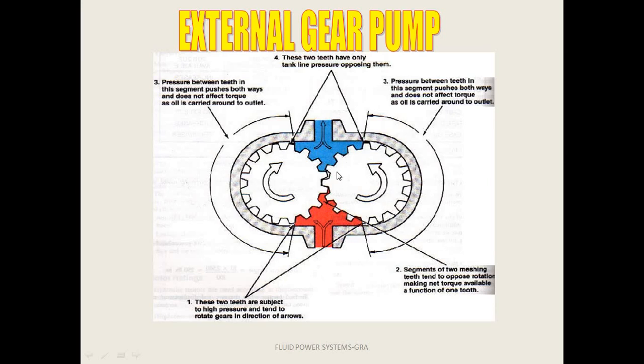Right? The second limitation is the volumetric efficiency of gear pump is very less. What I am trying to say here is, from this outlet side to the inlet side there will be leakage. Whatever the fluid will be coming here, a part of it will drain back to the inlet side, and because of this the volumetric efficiency is very less.